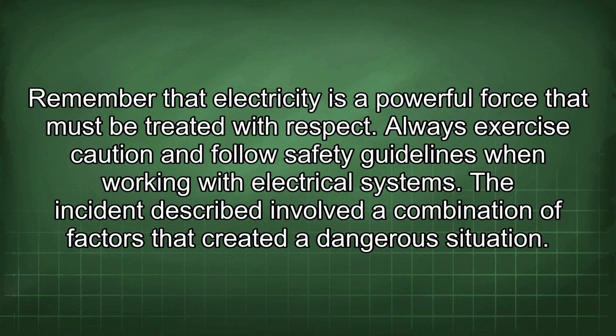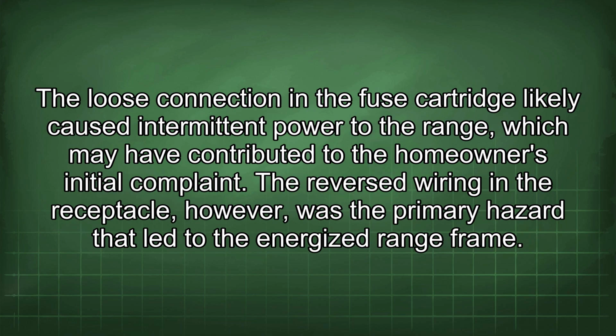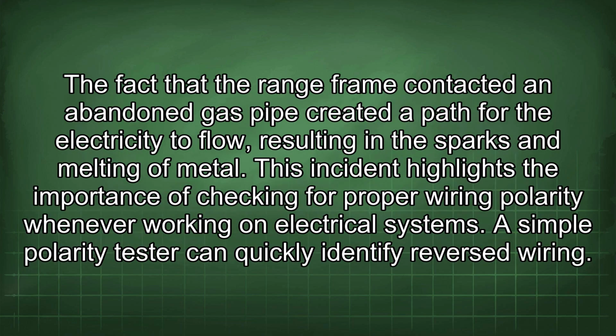The incident described involved a combination of factors that created a dangerous situation. The loose connection in the fuse cartridge likely caused intermittent power to the range, which may have contributed to the homeowner's initial complaint. The reversed wiring in the receptacle, however, was the primary hazard that led to the energized range frame. The fact that the range frame contacted an abandoned gas pipe created a path for the electricity to flow, resulting in the sparks and melting of metal.